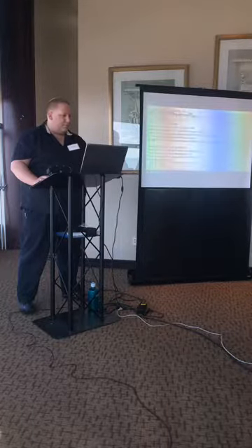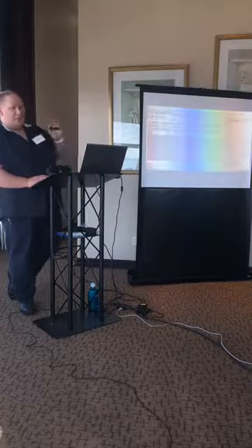And I'm not sure why it's not doing my BEP calculation. There we go. Sometimes if you just reopen a window and click OK, it'll do what you want it to. And so you can see here that it's operating at about 99% of the best efficiency point. It's going to be a really solid operation, not going to be having a lot of vibrational problems and whatnot, and you're getting an efficiency of about 75%. So that's how you go through and size the pump.